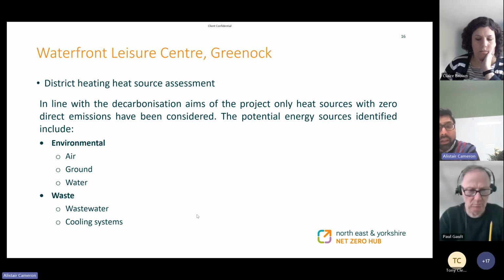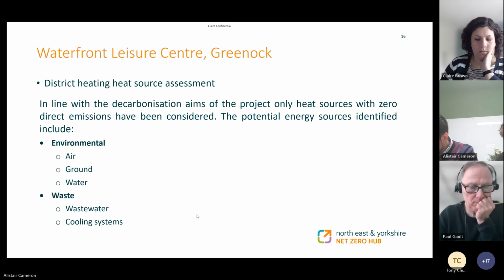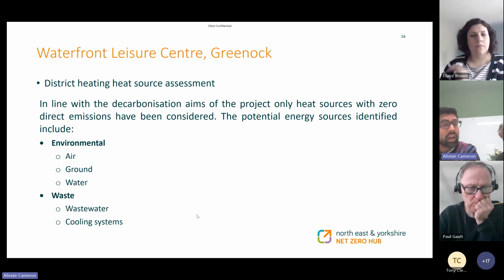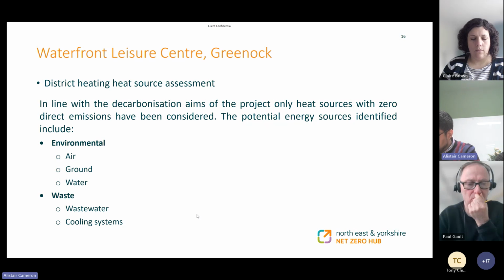The building itself, the waterfront, is blessed because it's adjacent to a river, the Clyde. So there were opportunities there to utilise the water by having some water sourced heat pump solution. And there's also good ground conditions around the waterfront leisure centre. There are large car parks and green areas. So again, we could look at ground source heat pumps, either open loop or closed loop. And the other option would be to use the air and have air source heat pumps. So that's taking advantage of the environmental opportunities in and around the building itself.